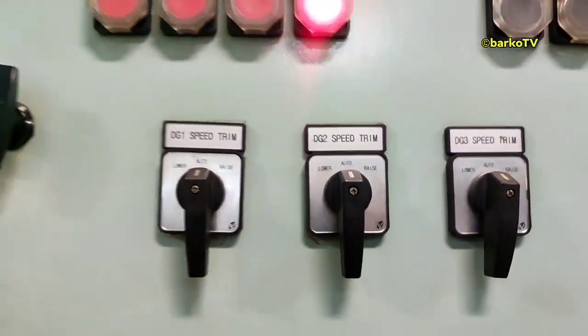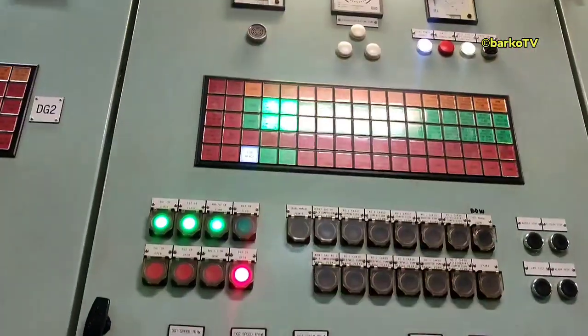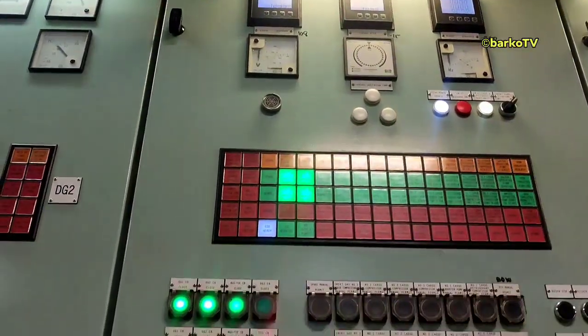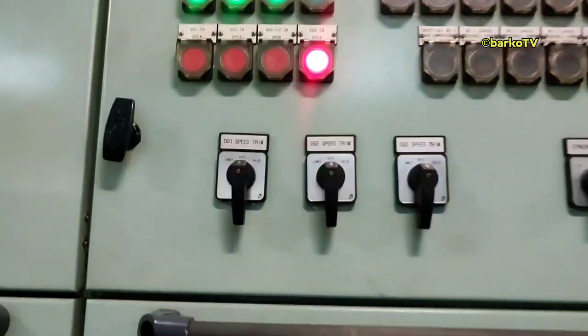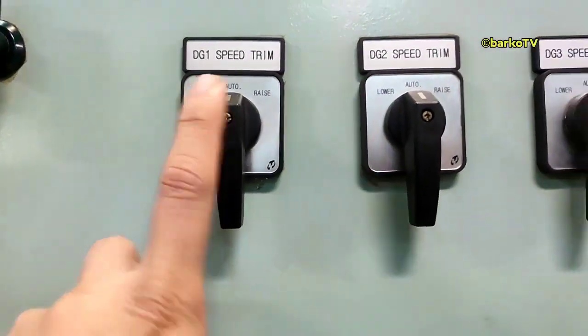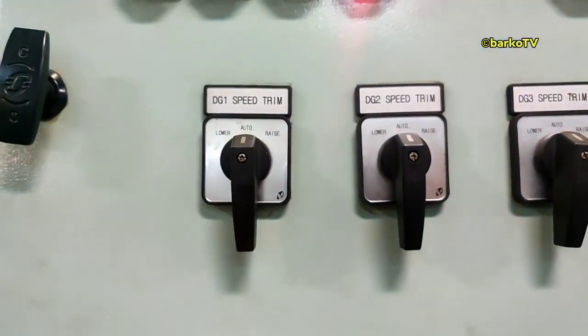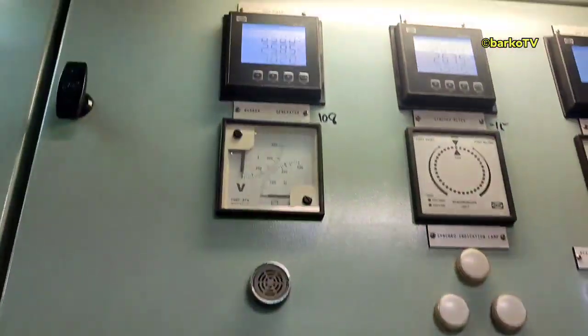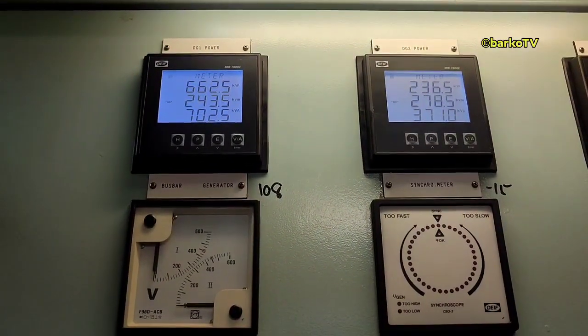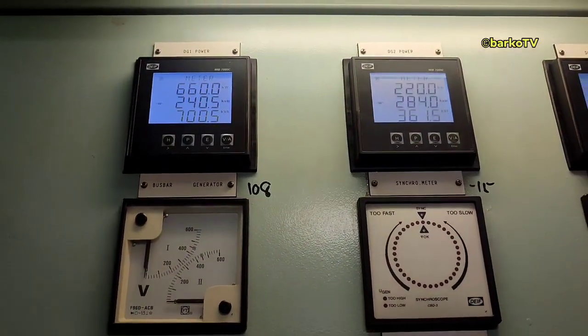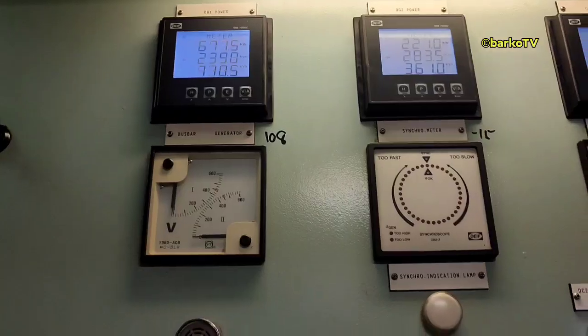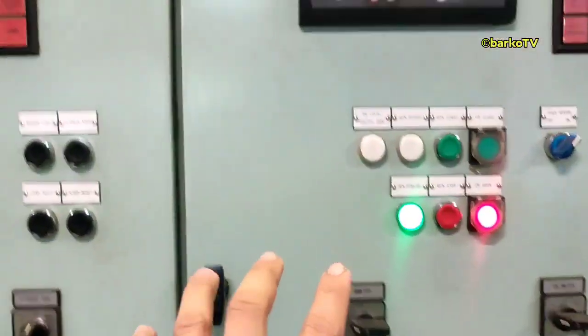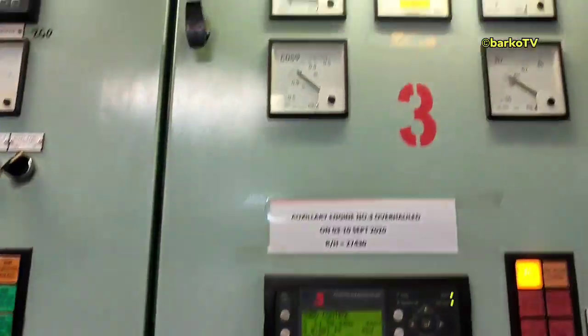If in auto, raise means you add more load to your generator, and lower means decreasing load. If two generators are synchronized manually, for example one and two synchronize with each other, but the mode is manual, if you raise number two, then number two will get the load from number one.